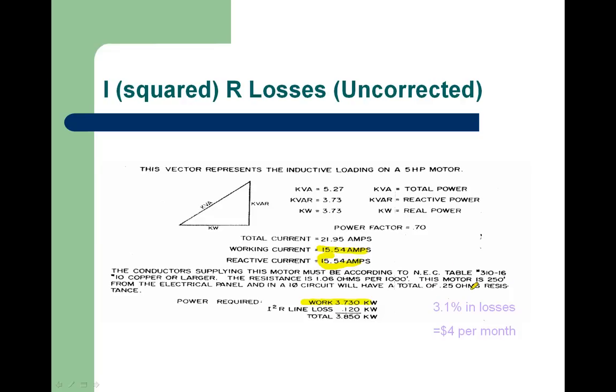That right there, yes, 250 feet. It's a number 10 wire, so it would be about 2/3 loaded. If we moved that 250 feet away, we would actually have some line losses right here of about 0.12 kilowatts. So if the motor was at the main switchboard, we would be registering 3.73 kilowatts on your hydrometer. If we moved it out 250 feet, you would actually be measuring 3.85 kilowatts. If we look at this, it amounts to about 3.1% in losses, which, if this motor was running for a month, would be about $4 in losses for that particular motor.